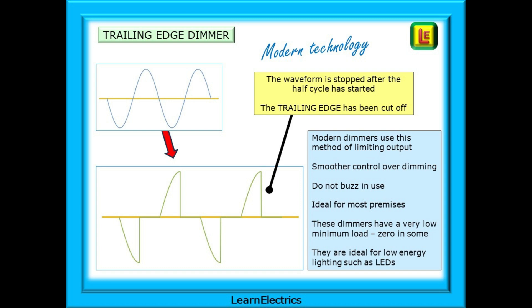And then we have trailing-edge dimmer switches — completely different, using more modern technology and different methods of manufacture. The waveform starts at zero and is then stopped after the half cycle has started. The trailing edge, the last bit, has been cut off. Modern dimmers use this method of limiting the output. It gives smoother control over dimming, and the switches do not buzz in use, making them ideal for most premises and situations. These dimmers have a very low minimum load, all the way down to zero in some switches, and they are ideal for low-energy lighting such as LEDs.